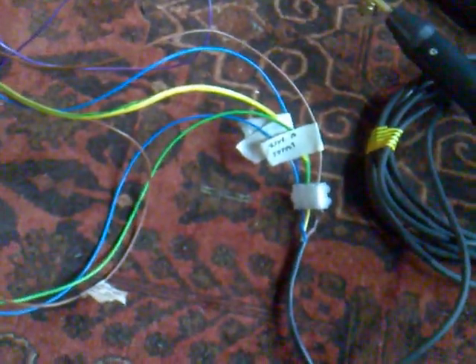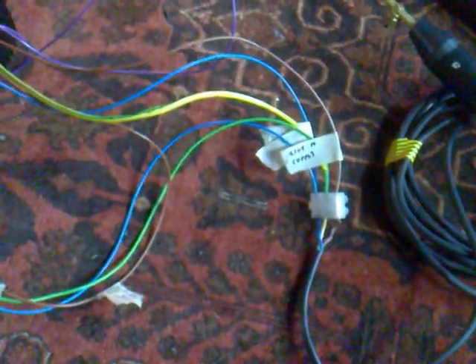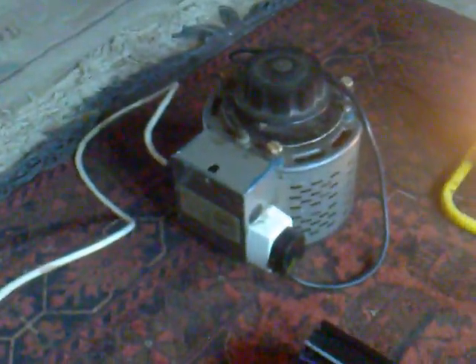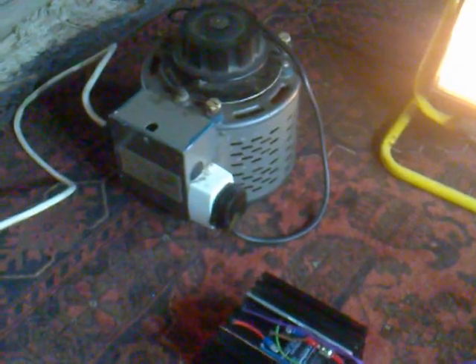Simple, reliable, and wire it in yourself. 3 wire to the junction block there that goes to your transformer. Your supply there, make sure you've earthed absolutely everything in sight, anything you can touch anyway, and the whole lot will need to be installed in the box with the transformer to protect it from polystyrene debris, which could cause the transformers to overheat because their cooling gets blocked up. So we need to keep the fine debris out.